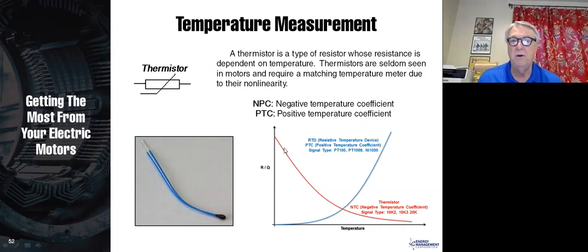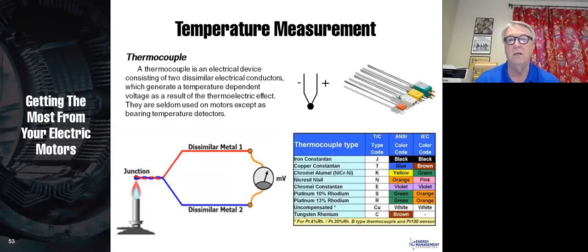So if you're going to use a thermistor, you really have to have something where, let's say you're using it on a variable frequency drive, and you're connecting this thermistor to the variable frequency drive. It's going to have to know that whole curve of the particular thermistor you're using in order to know what the temperature is. Some drives actually have a thermistor input as a standard, and we do see this, particularly in OEM equipment where they're using the same motor on the same device constantly.